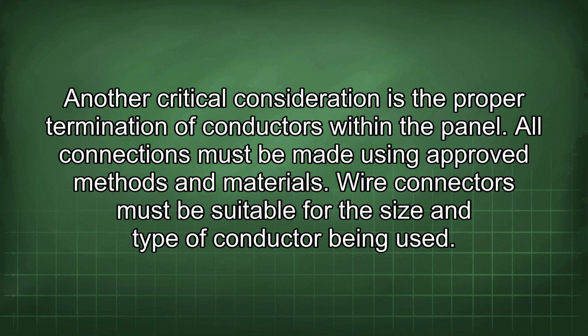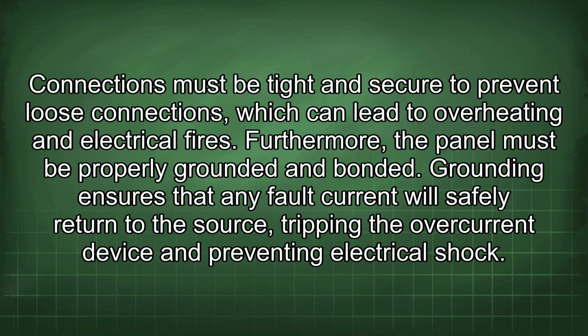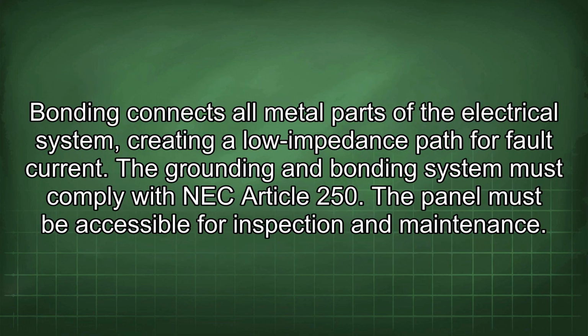Another critical consideration is the proper termination of conductors within the panel. All connections must be made using approved methods and materials. Wire connectors must be suitable for the size and type of conductor being used. Connections must be tight and secure to prevent loose connections, which can lead to overheating and electrical fires. Furthermore, the panel must be properly grounded and bonded. Grounding ensures that any fault current will safely return to the source, tripping the overcurrent device and preventing electrical shock. Bonding connects all metal parts of the electrical system, creating a low impedance path for fault current. The grounding and bonding system must comply with NEC Article 250.